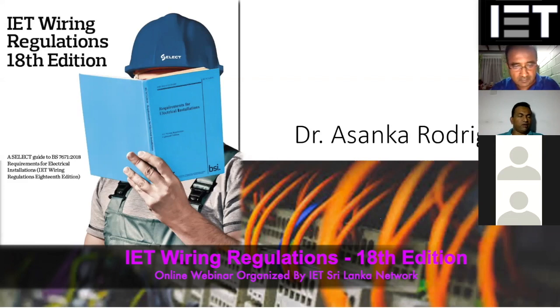If I remember correctly, when you are checking the insulation levels, those levels will depend on the different voltage values. I cannot exactly remember what the values were, but there are 3 different levels: ELV systems, LV systems and high voltage systems. Therefore, for each and every voltage there is a minimum requirement, and they have to comply with those minimum requirements for the IR values.